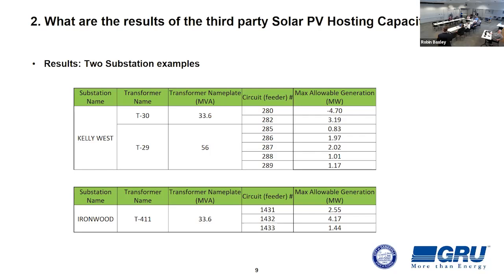And so what do we glean from this? What we glean from this is, while our original thought was 2 megawatts, we feel that's still a good number without having to perform a study. But as you can see, depending on the loading of the circuit and the characteristics of the circuit, you may be allowed to connect more than 2 megawatts in some cases, but in other cases, you may be limited to less than 2 megawatts. So that's why it's important when we start getting close to 2 megawatts, we're probably going to start asking our customers, as written in section 8, do you want to pay for an impact study so we can be sure, for this particular circuit, what is the maximum and can you add what you're requesting to add?